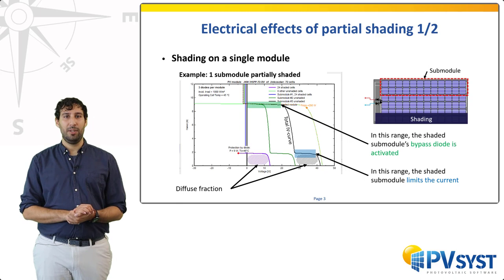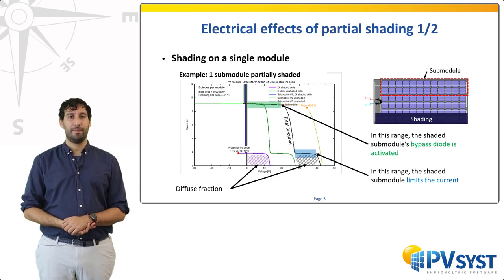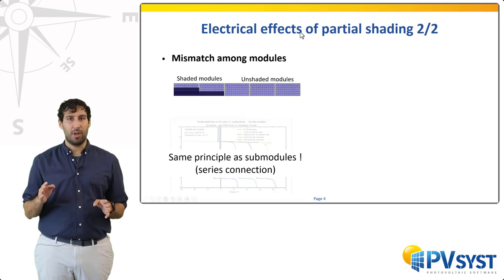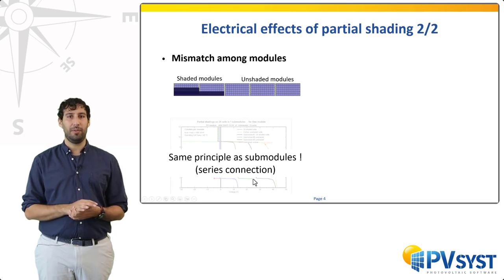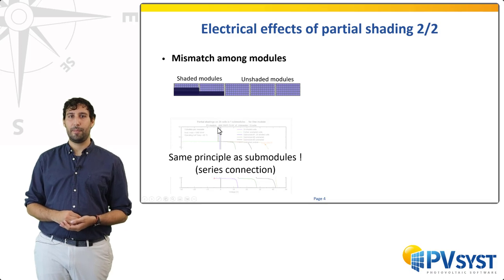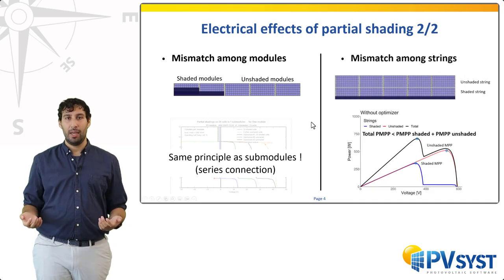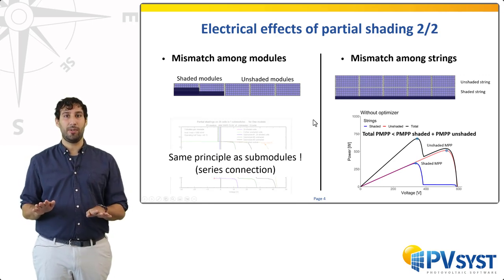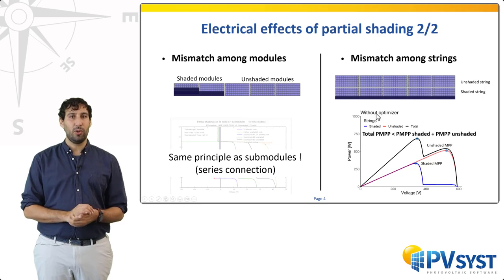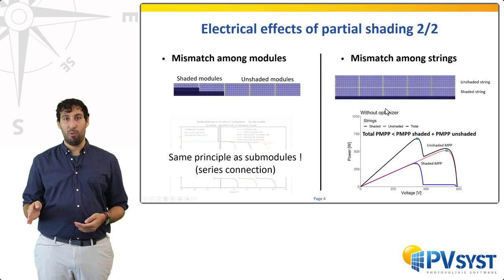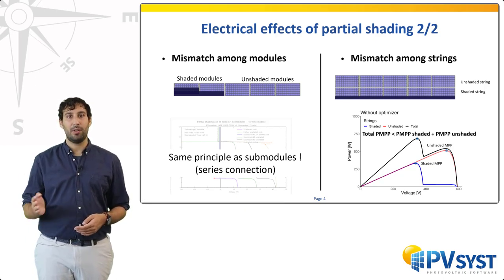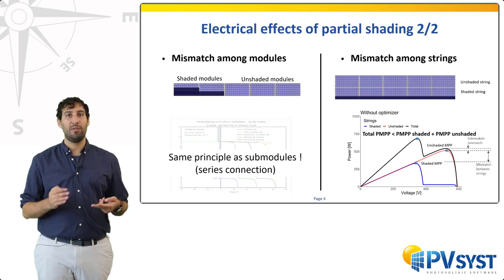Once we connect multiple modules together into strings and inverter circuits, other types of mismatch can arise. If the shadings are inhomogeneous among modules of a same string, there will be a certain mismatch between modules. The behavior is, however, basically the same as with submodules — after all, you still only have components in series. Mismatch between strings is different and can also become important. There may be a certain voltage mismatch between MPPs. In this example, a shaded string is in parallel with an unshaded string. The respective maximum power points are at different voltages due to some bypass diodes being activated. The total maximum power point is situated at the level of the lower voltage, but in doing so, the total maximum is not the sum of the maxima. Here, one will suffer both from the submodule mismatch — i.e., loss of part of the diffuse production — and from the mismatch between the strings.